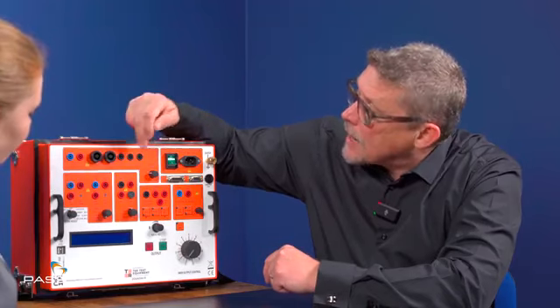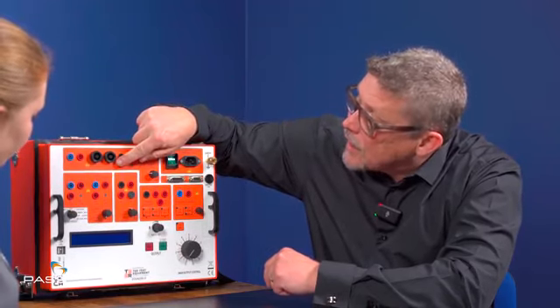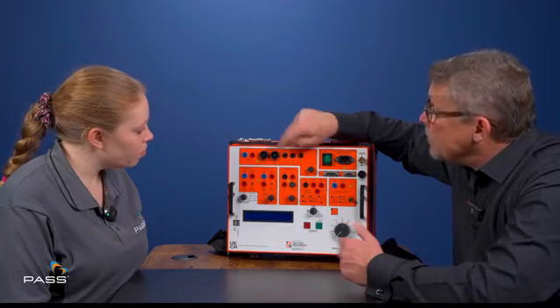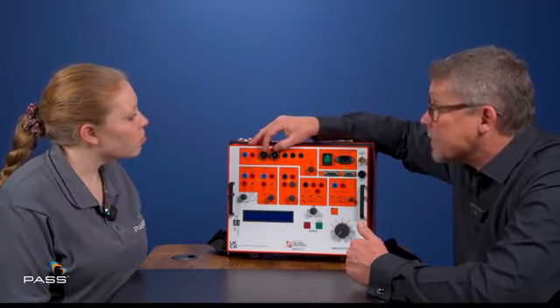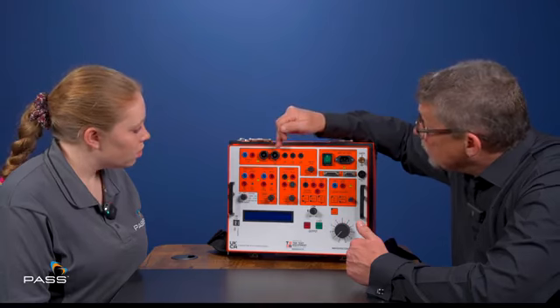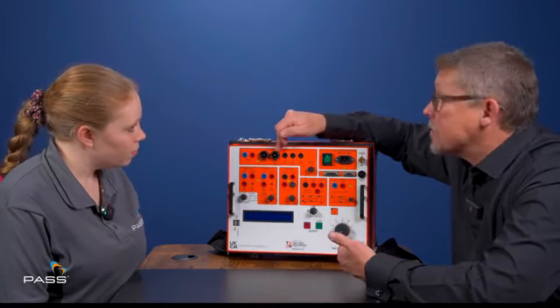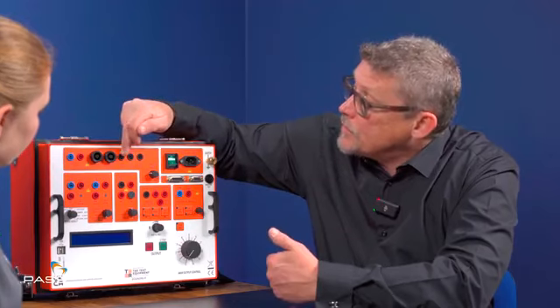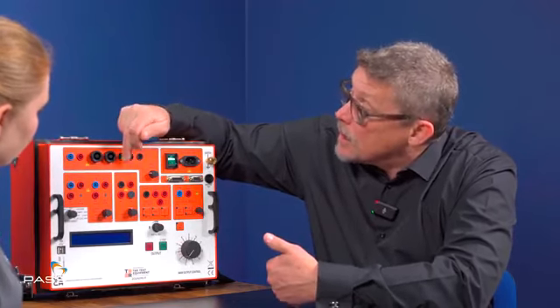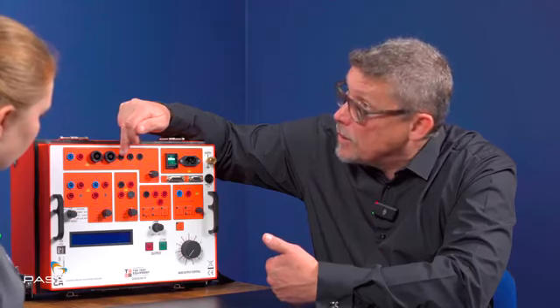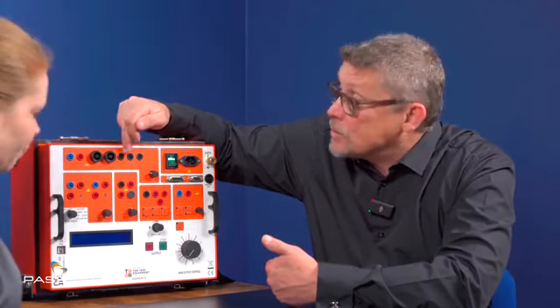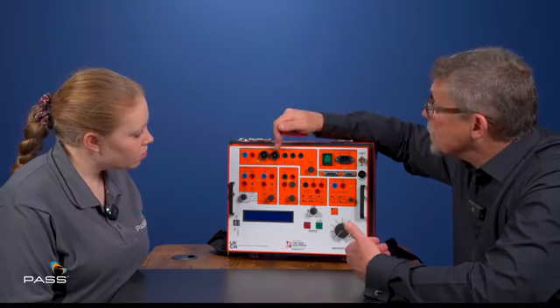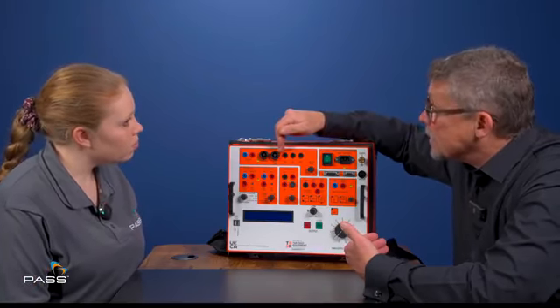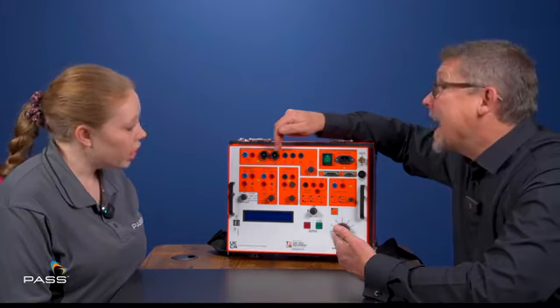Yeah. Now, if we drop down a tap, you'll notice this is a 200 amp tap at 10 volts. So bottom line being, this is going to give you 2000 VA max. But to get more current, if the 10 volts is not giving me the current because the resistance of the circuit's higher, then I can drop down one tap and I can get that current because I'm now dropping down a tap in current, but I'm going up a tap in voltage and so on and so forth. So what I always say is try for the highest voltage that will give you the current that you're looking for. If you're close to that current, maybe still drop because this has a little bit extra under the hood.